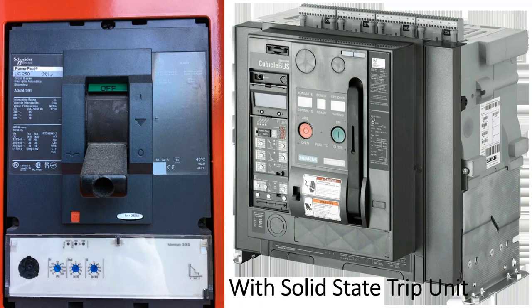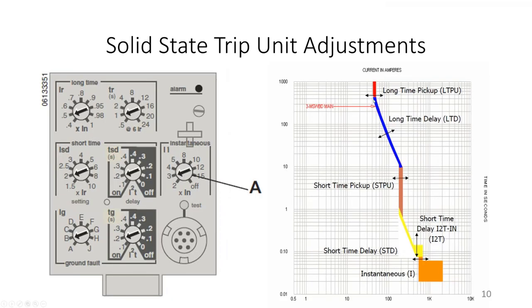I don't like that most of the time I see studies from other people whose recommendation will be, okay, add a solid state trip unit and it's going to solve your problem. I have to admit I have done that too in some jobs, but it's not always the answer. It's not always going to solve the problem. Yes, I can take a solid state trip unit and have all these different areas of the TCC changing where and how it's going to react. But it depends on what you have upstream and downstream, and that is going to limit whether this works.